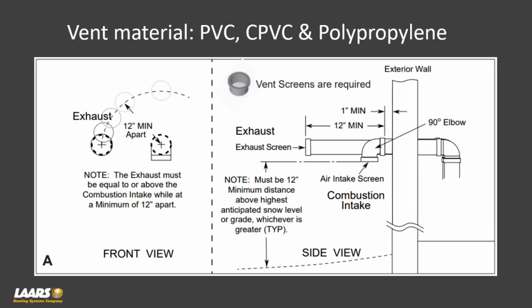And we can be in two different pressure zones. What I mean by that is we can take combustion air from the space, such as a basement, and just vent outside. Or we can bring combustion air from a sidewall and vent through the roof. Or the east wall, bring combustion air, west wall, exhaust. So we can be unbalanced, in two different pressure zones. Again, you can go 100-foot exhaust and 100-foot combustion air in 3-inch vents. So again, 100 of each.